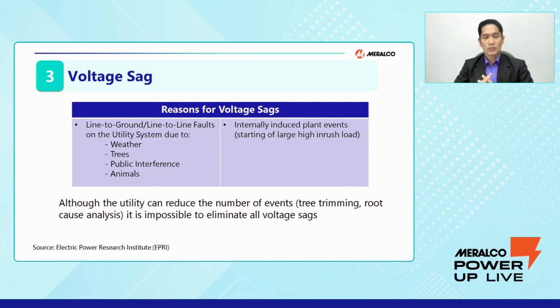So the reasons for voltage sags are faults, either line to ground or line to line faults in our distribution system, due to weather, trees, public interference, animals. Public interference is not only limited to construction, but also to kite flying and balloon strings that will affect our distribution lines. And also internally induced events in our facilities and plants due to starting of large inrush loads, especially if we do not have a reduced voltage starter for our motors.